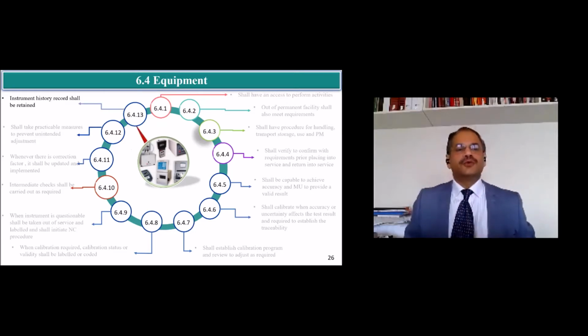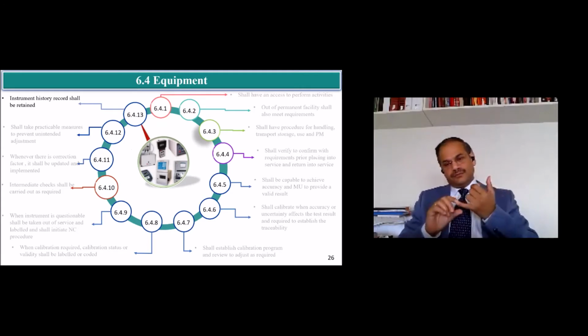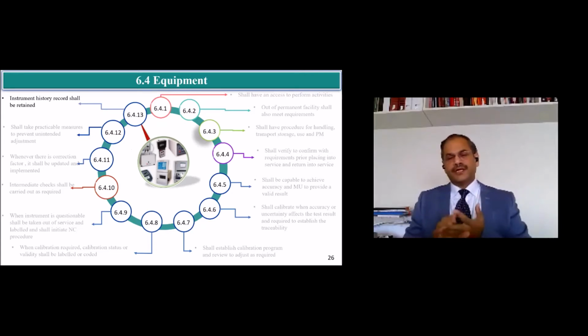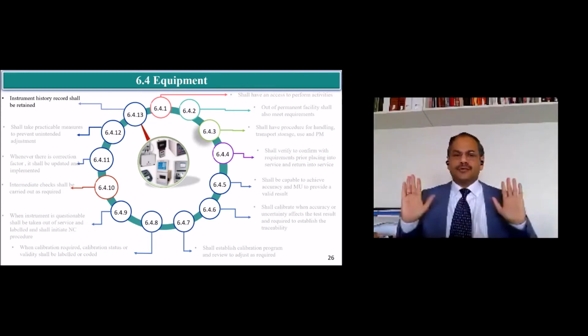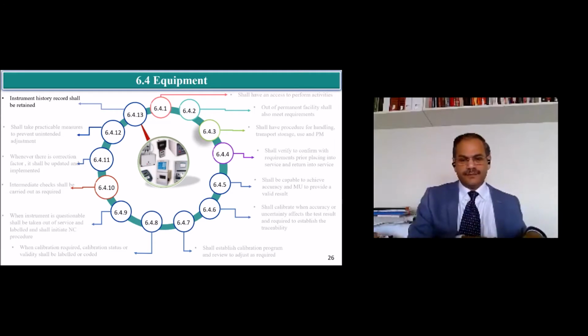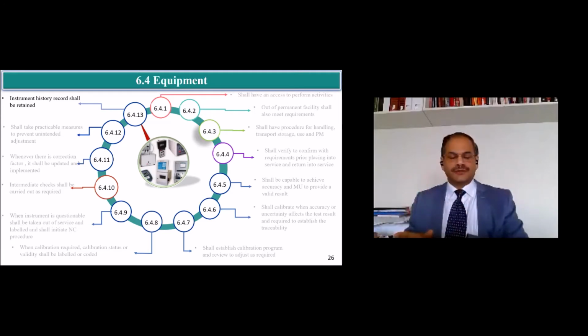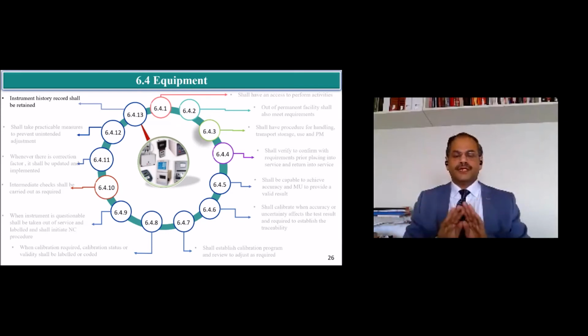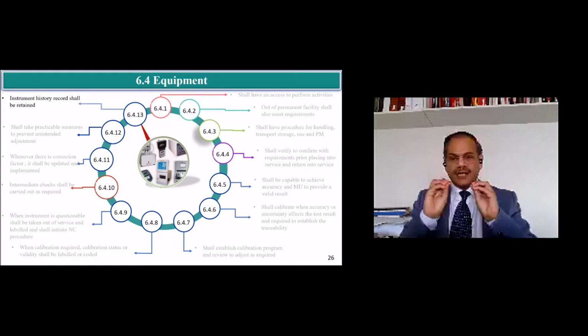Now, instrument history has to be retained: the commissioning report, the instrument manual, who is competent to perform the test, how to handle it, what the calibration frequency is, when was the last calibration, when is my next calibration, when PM was done, what troubleshooting was done. All this history has to be maintained. How do you maintain the history? It is up to you. You can have hard copies or you can have a LIMS. It is perfectly left to you. They are not saying how to do it. They say all the history has to be maintained.